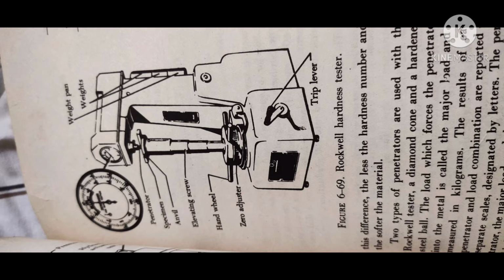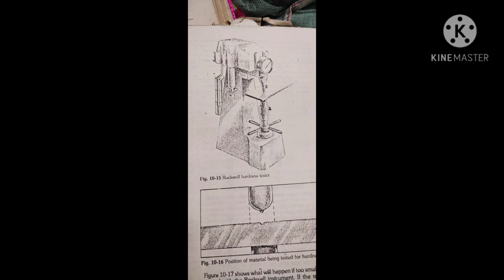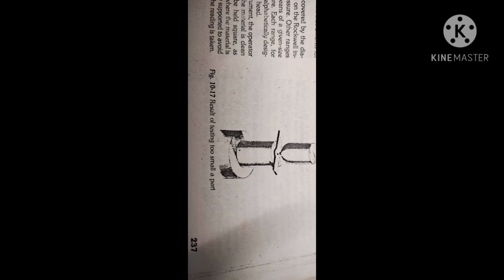Rockwell tester. The Rockwell hardness tester, as shown in the figure, measures hardness by resistance to penetration as does the Brinell tester. Instead of measuring the diameter of the impression, the Rockwell tester measures the depth, and the hardness is indicated directly on a dial attached to the machine. The dial numbers in the outer circle are black and the inner numbers are red. Rockwell hardness numbers are based on the difference between the depth of penetration at major and minor loads. The greater the difference, the lower the hardness number and the softer the material.